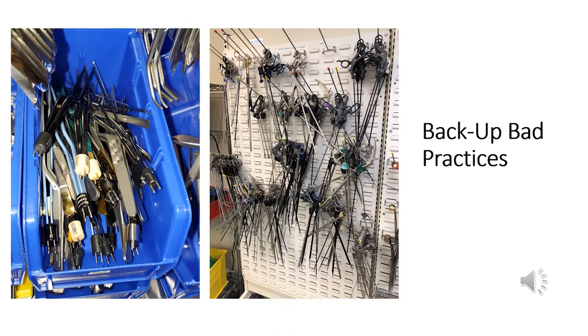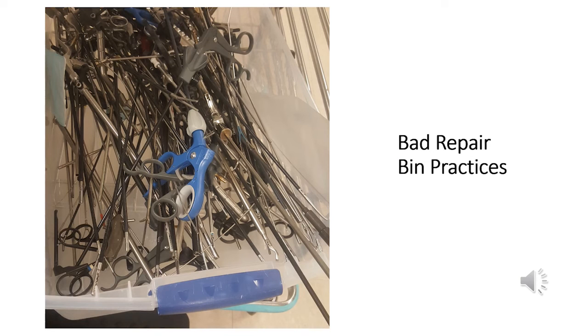Repair bins are a big issue because you're sending out instrumentation that already has damage to the insulation itself. But when you have so much like this in a bin, you're causing more damage, possibly not even to the insulation, but to the distal end or even the handle of the instrument. So I definitely recommend separating your damaged insulation by category. Maybe forceps would be in one bin that only holds about 10, and then you send it out, separating your forceps and other insulated devices.